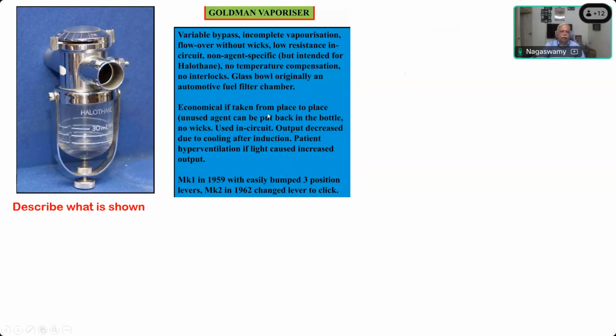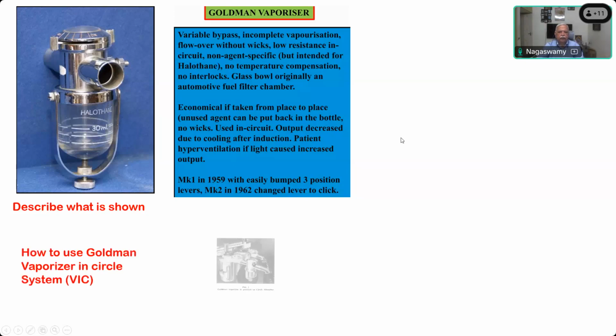It is economical, and you can carry it from place to place because it's portable. Used inside the circuit, output decreased due to cooling after induction. Patient hyperventilation increases the output. And Mark 1, the model from 1959, had 3 positions. It has the on and off lever. By rotating it, you can use the off position. Then there are 1, 2, 3, and 4 positions which you can open. So it is a variable bypass: the fresh gas flow will come through, take the vapor, and come out. And in Mark 2, it was changed to a lever with a click. So this is the modification that was done.